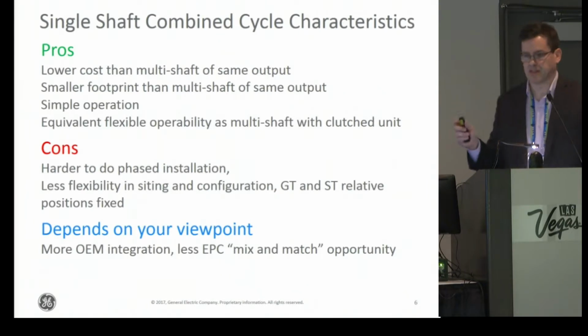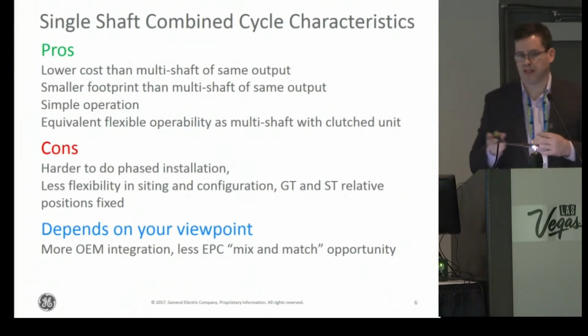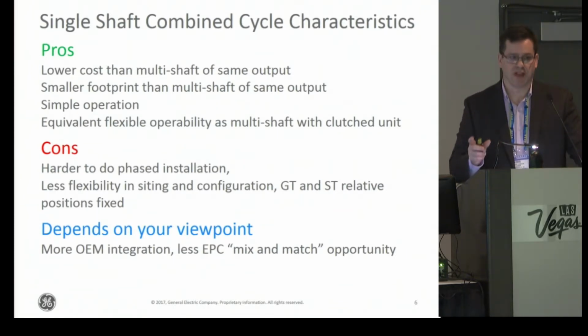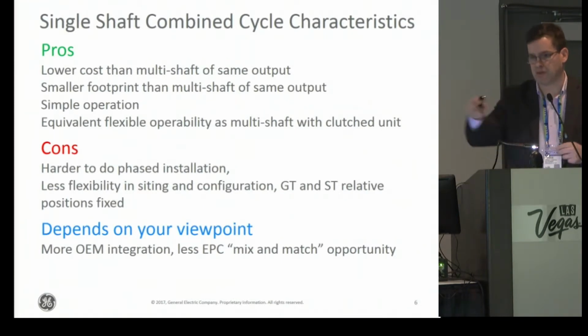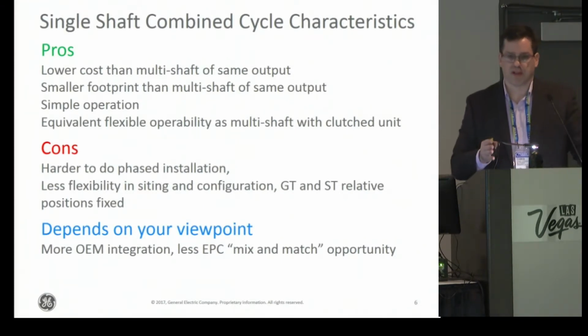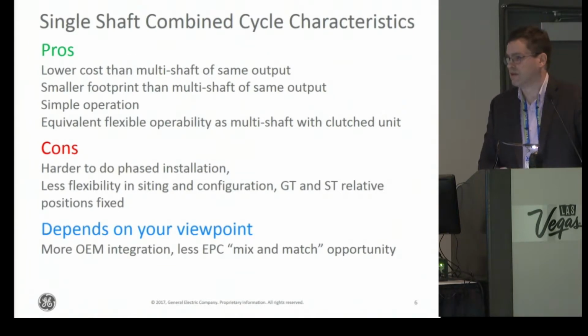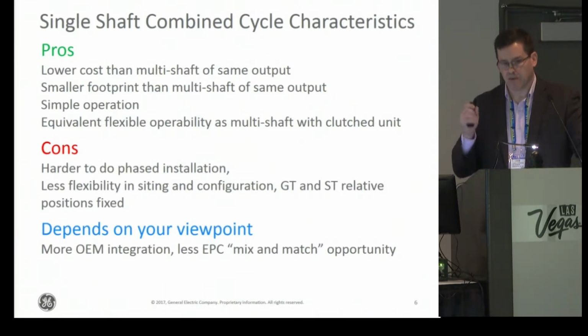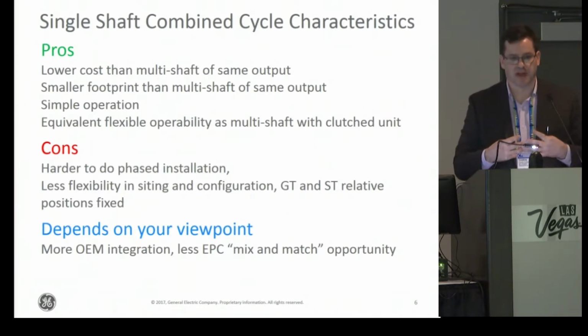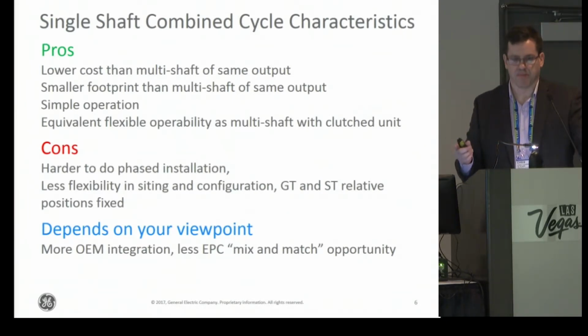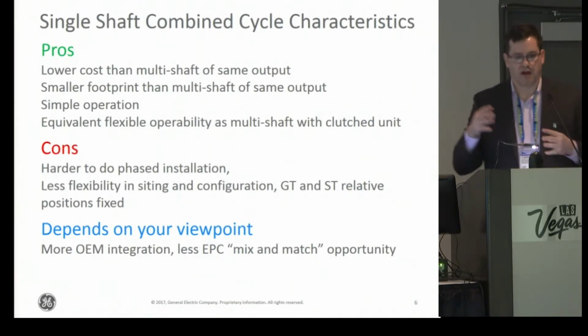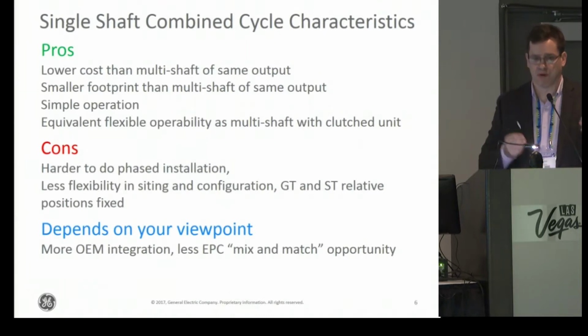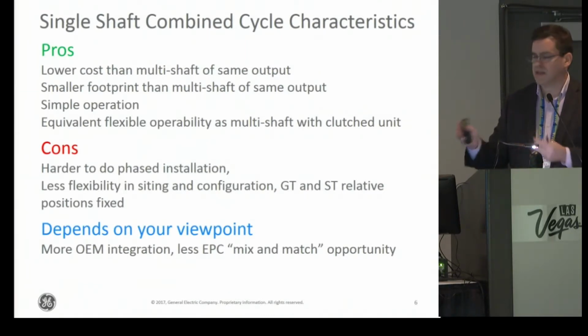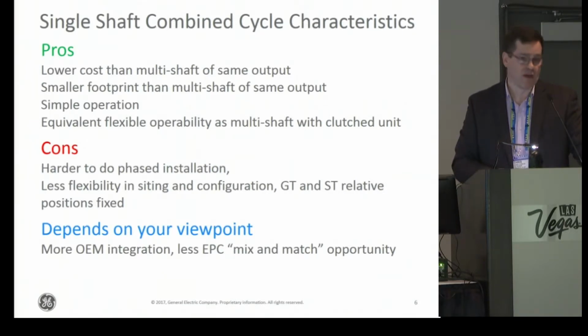Also, although the single shaft has a smaller footprint, if you have an unusual plot plan, if you have to be creative in your location of the steam turbine, that's harder to do with a single shaft. You're pretty much locked in. But with a one-by-one multi-shaft, you can move that steam turbine around if you want to, perpendicular to the gas turbine center line, parallel to the gas turbine center line, whatever fits that particular application. And then there's some features of it. It requires more OEM integration because everything's coupled together straight up. For some people, that may be a plus because you get that OEM integration. But other customers or other markets may want to bid out that equipment separately. So it depends on your viewpoint whether you want more or less OEM integration.